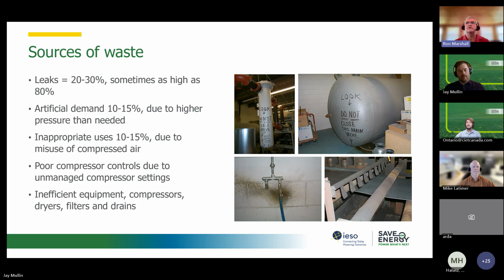Hope that answers the question. Yeah, I think so. And also, whether you're operating at full load or part load can influence that specific power as well, depending on how the system's controlled, right? Because in some compressors, they don't turn down very well, so you might have a higher specific power if you're at like 60% capacity than if you're at full capacity. Is that accurate? Yeah, that's accurate. It depends on the control mode.